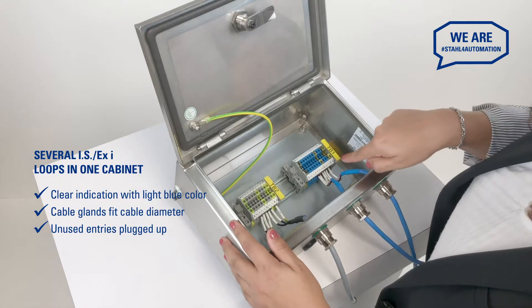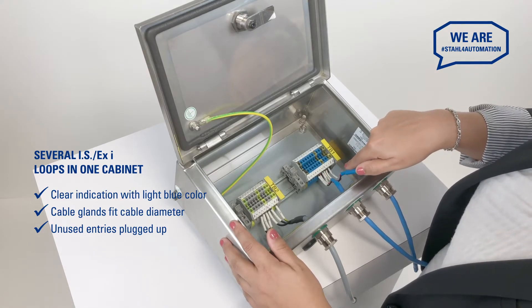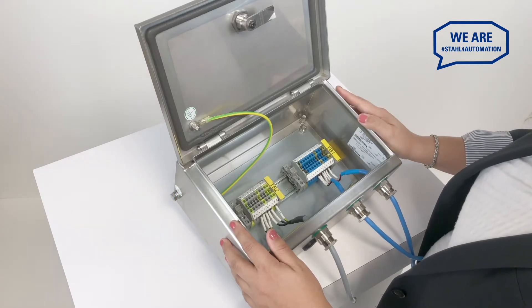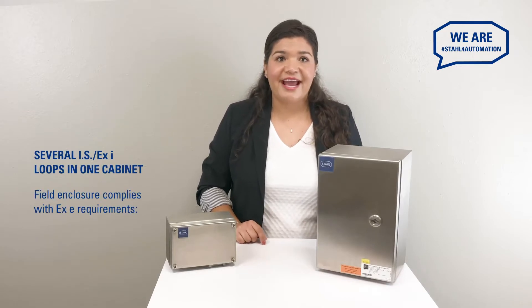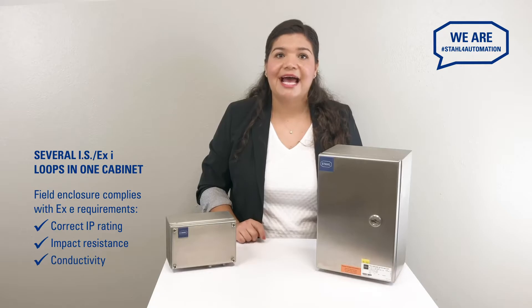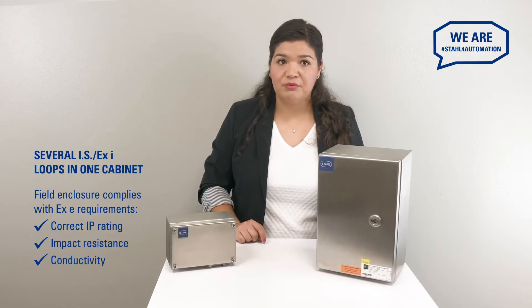A good practice when terminating cables is to use ferrules. This eliminates the possibility of strand separation and keeps installation simple. Your field enclosure must comply with the Ex e requirements and also feature the appropriate IP rating, impact resistance and conductivity for the environment it will be used in.